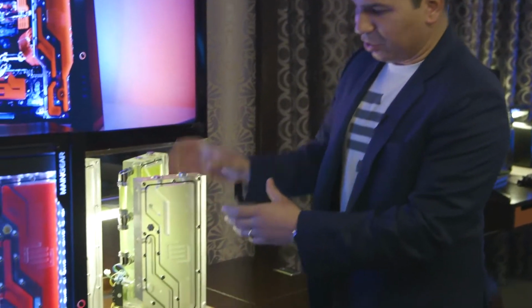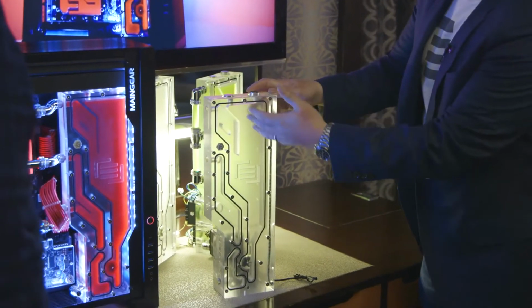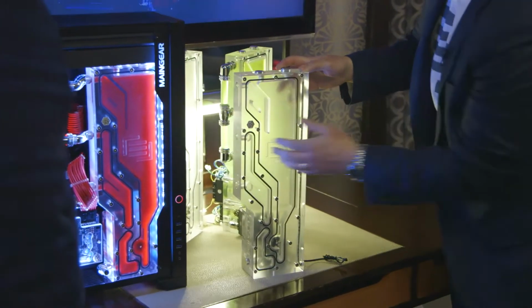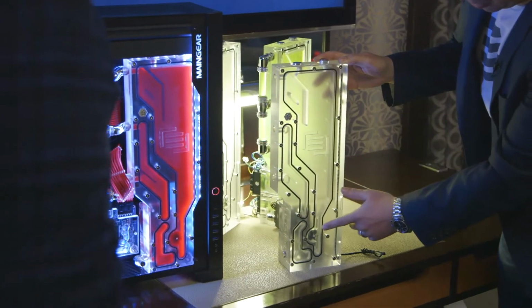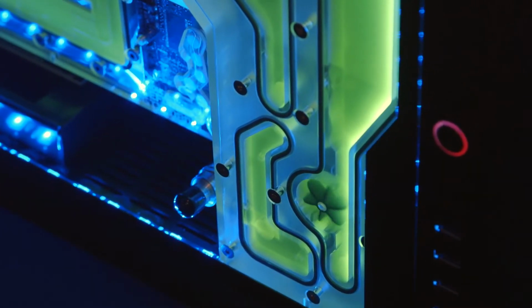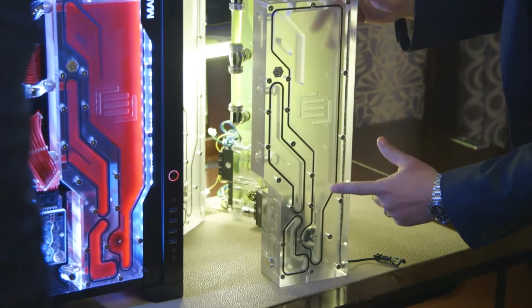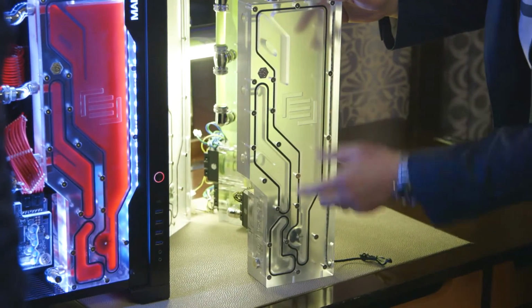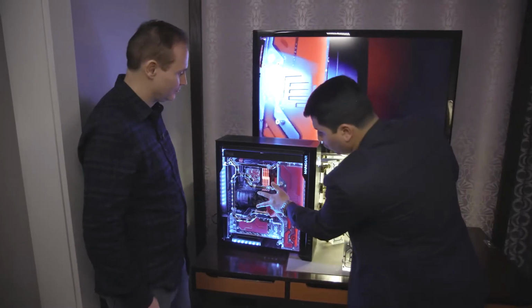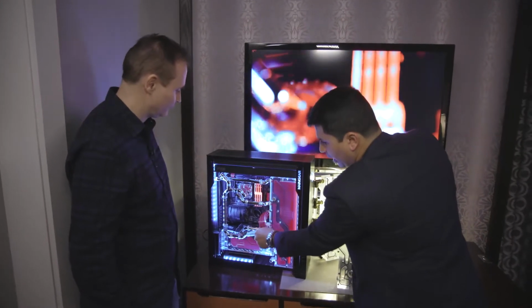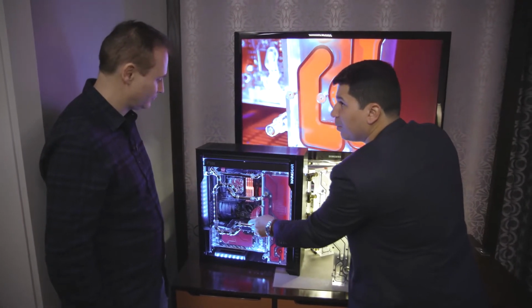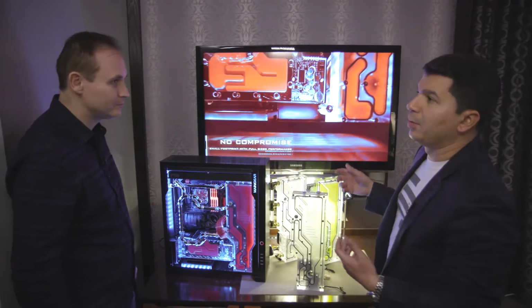Being that it's from scratch, we're able to do some really cool things. We eliminated the cylindrical reservoir, and this is a full-size reservoir, as you can see here, but it's fully functional. There's actually a flow meter here. The fresh water comes over here and disperses, gets pressure regulated, and throws fresh water into the CPU and the GPUs at the same time, making the liquid cooling loop parallel.